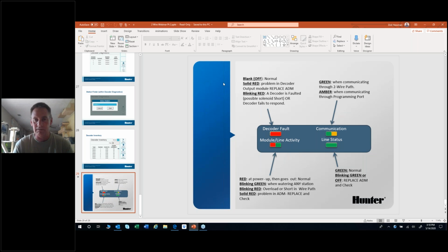The one right below it, module line activity: at power up, you'll see a lot of these lights blink, but only for a fraction of a second, then they'll go off. So you'll have a red at power up and then it goes out. That's normal. Blinking green means any station that is active out there is watering. If it's blinking red, you've got an overload or a short on the wire path, so that needs to be looked at. Solid red means you've once again got a problem with the ADM and need to replace it. That's a pretty common one to see blinking red when an ADM has gotten struck by something.